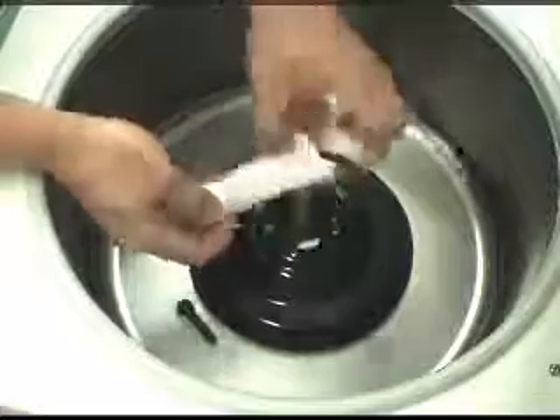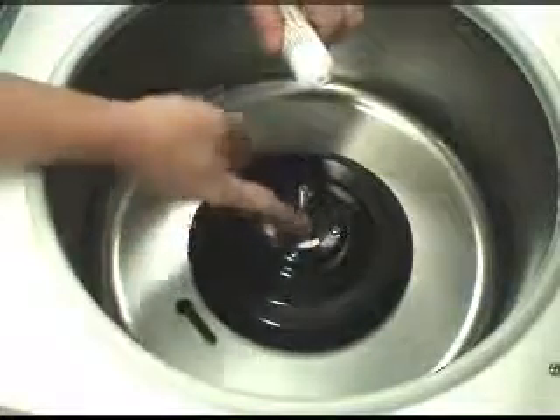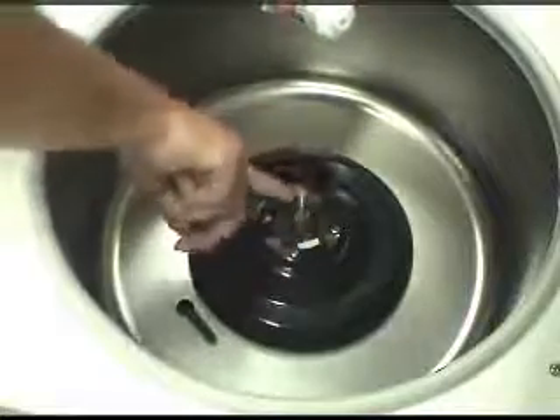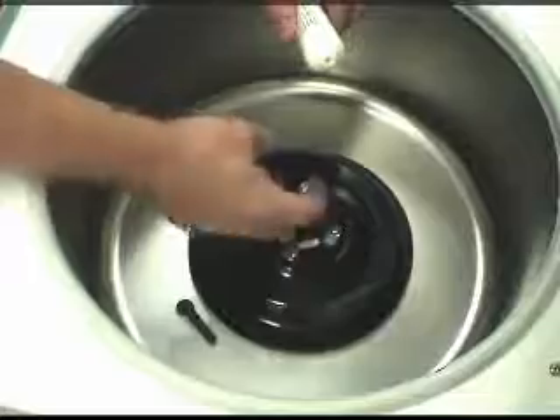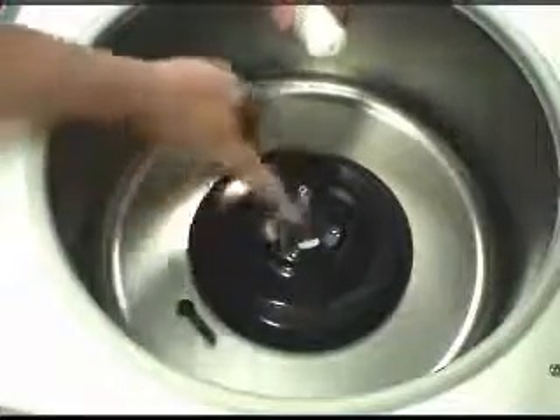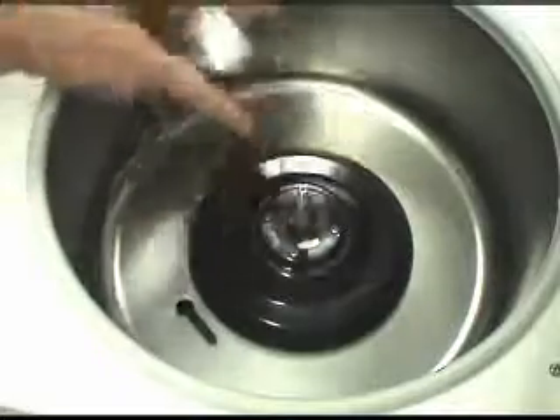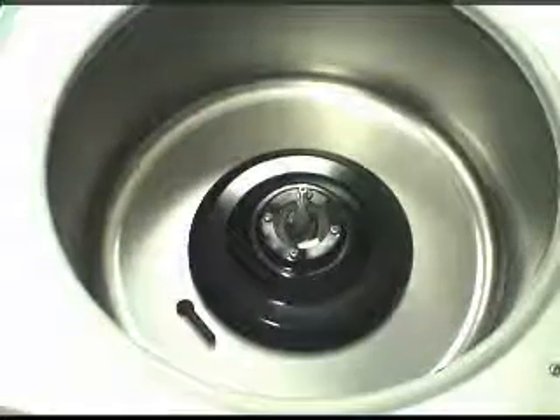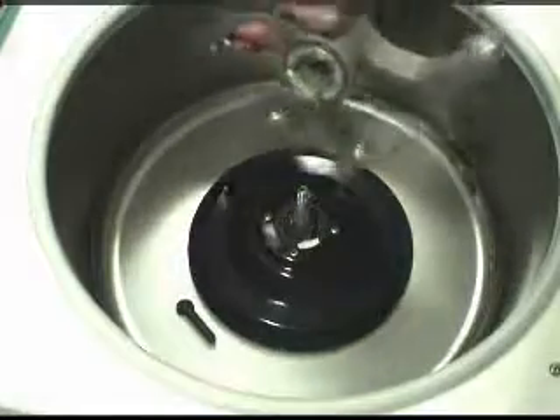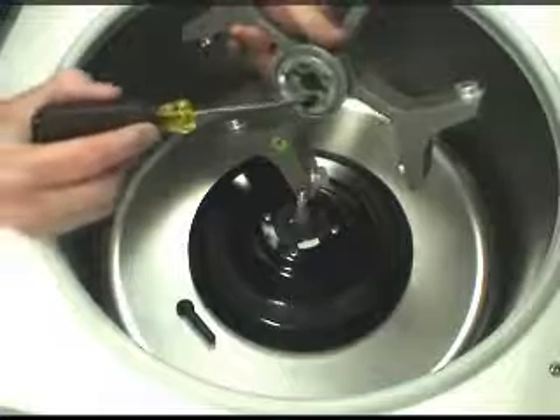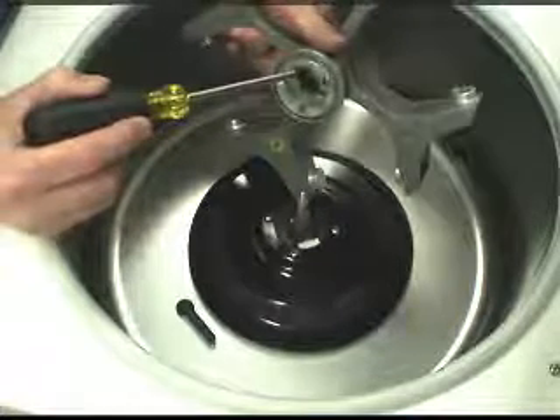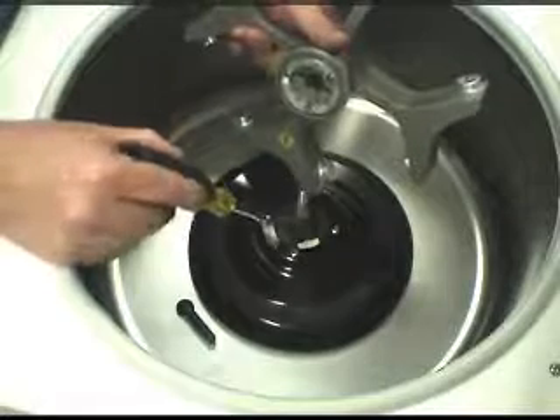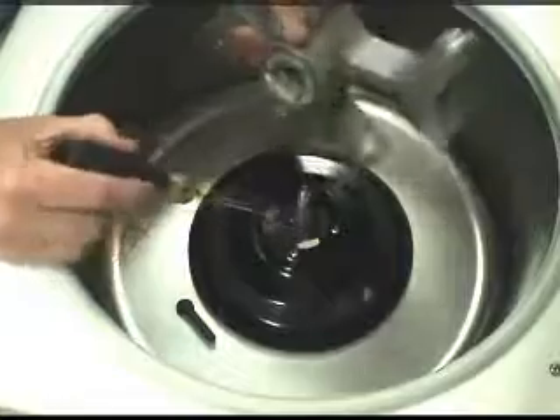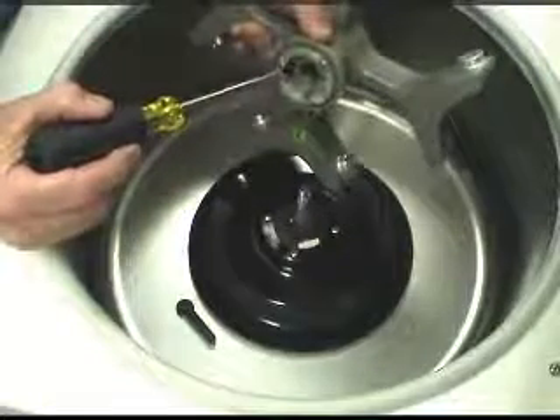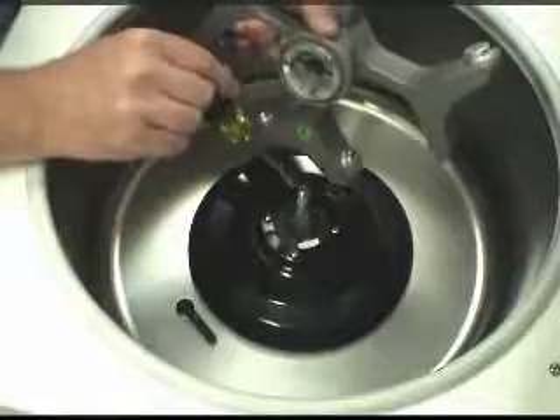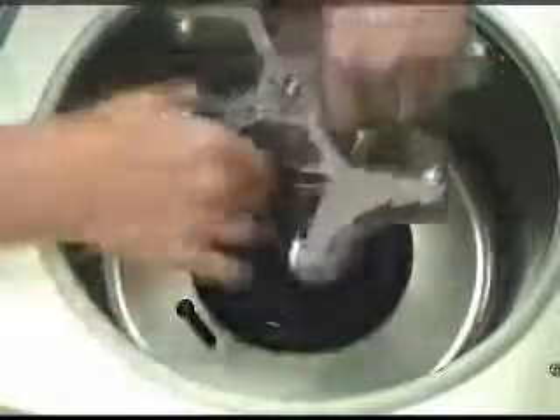Use some of the grease provided with the centrifuge to put a slight thickness of lubrication on the conical portion of the shaft to prevent metal-to-metal binding between the motor shaft and the rotor. This will help you to be able to remove the rotor at a later time. The rotor has a rotor ring under it, consisting of 6 magnets all the way around. This creates a rotor code that is picked up at this point here by the tachometer sensor. There are also alignment holes that fit the alignment pin on the motor shaft.